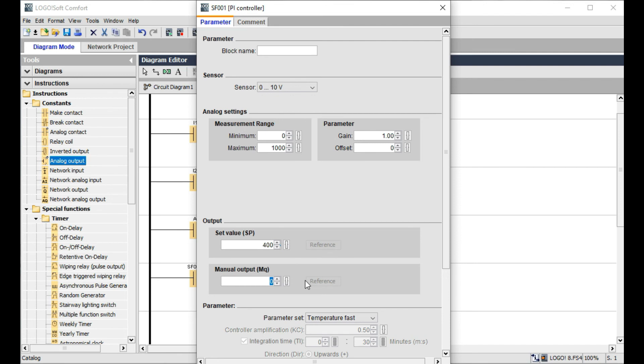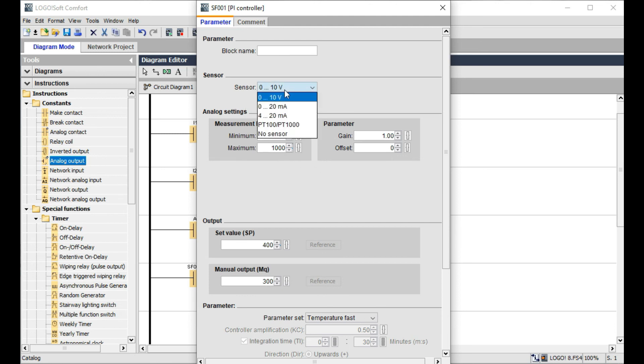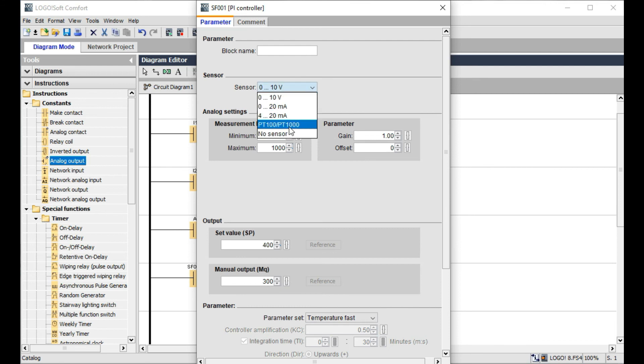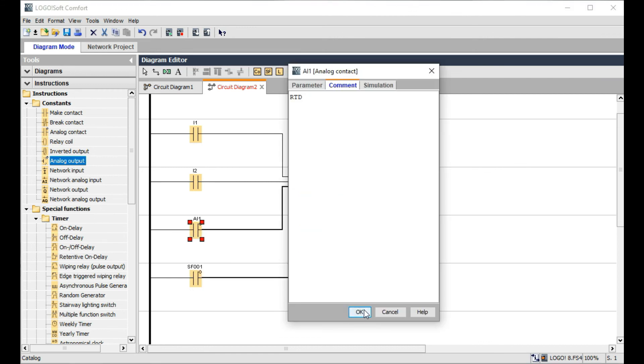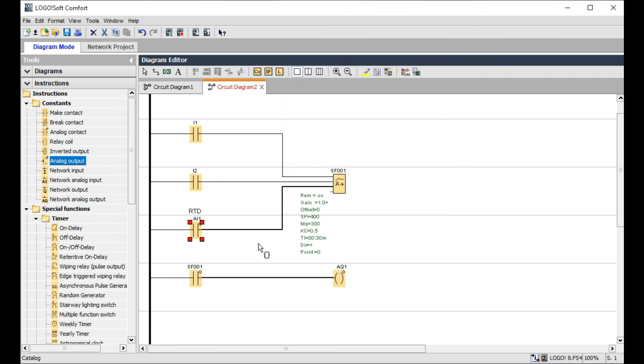The system is set to 300 for manual output, with a range of zero to 1000, corresponding to 0-10 volts. The processing value, such as from an RTD (resistance temperature detector), is configured. The set point is 400, the manipulated value is 300, and we observe the resulting process value. Let's go to the simulation.